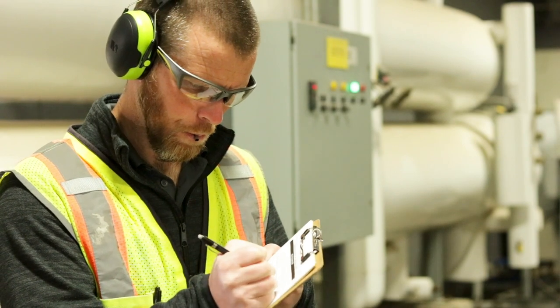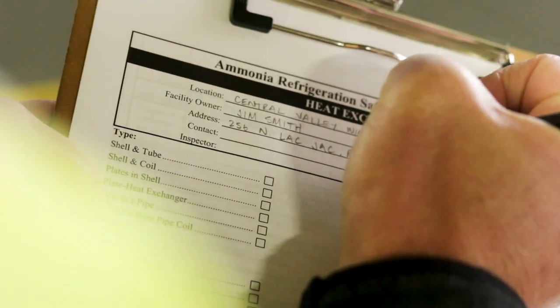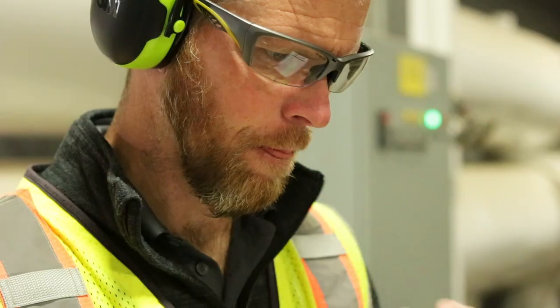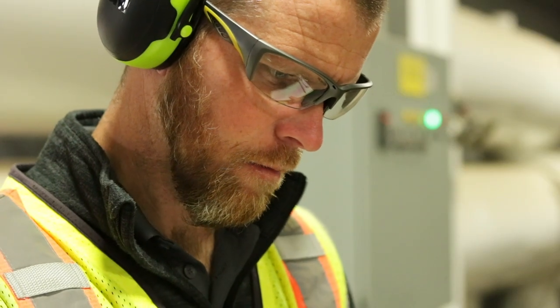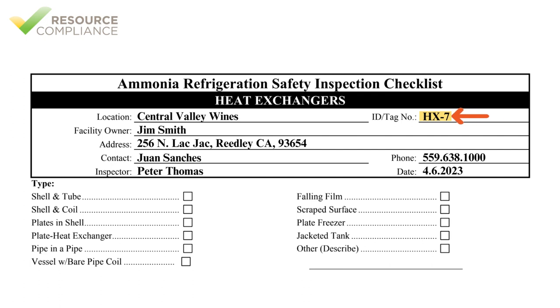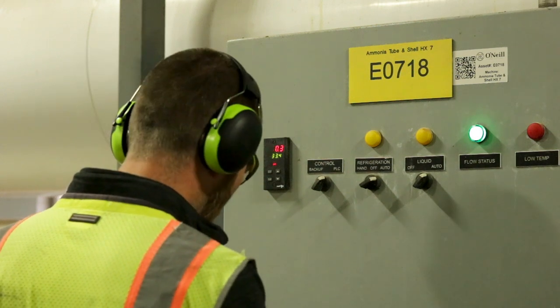The simplest part of completing a heat exchanger checklist is filling out the contact information. Each IIAR 6 checklist requires the inspector to indicate the location, owner, and physical address of the system. The contact's name and phone number should be the facility representative responsible for ensuring the inspection is completed. Additionally, the inspector must write his or her own name and the date of the inspection. The ID, or tag number, belongs in the upper right corner and can typically be found on the equipment label or P&ID.